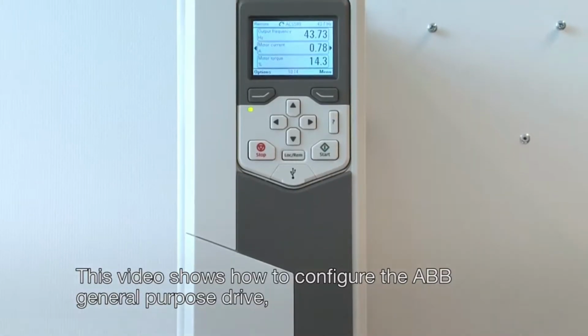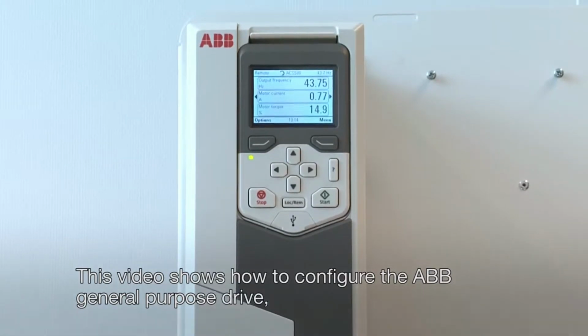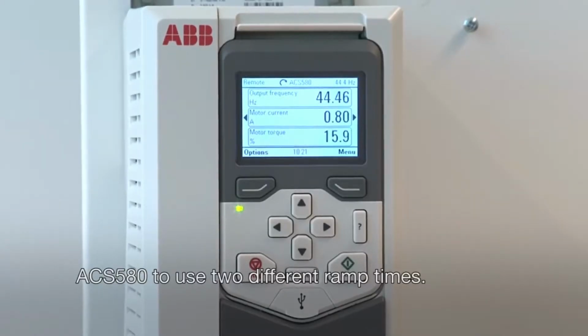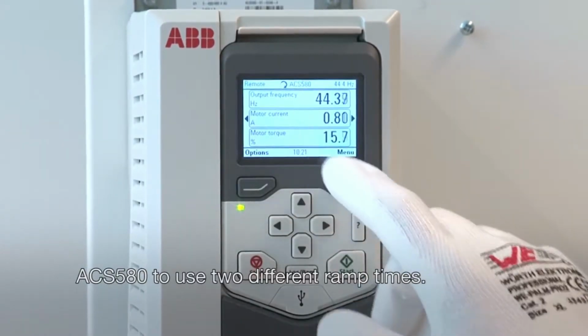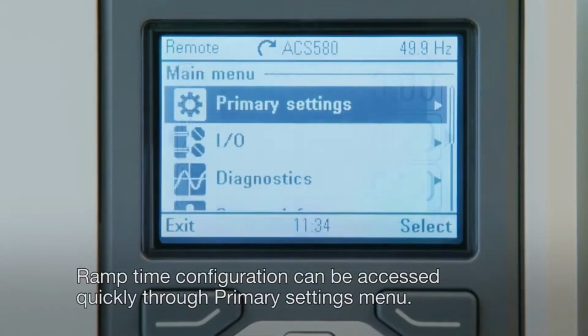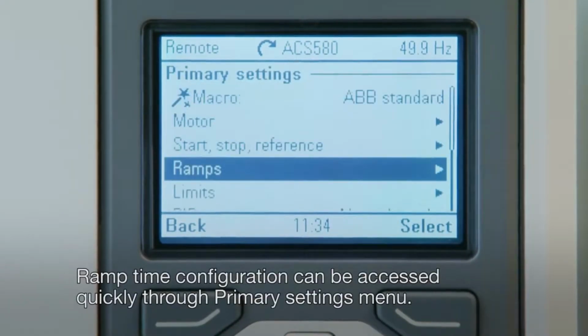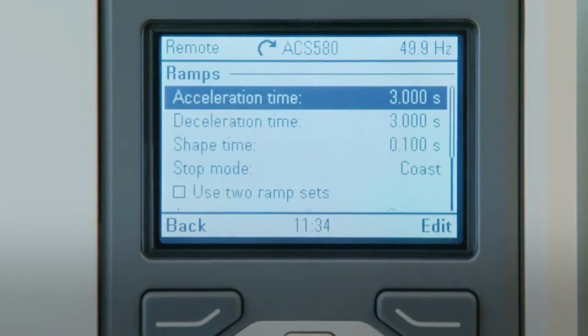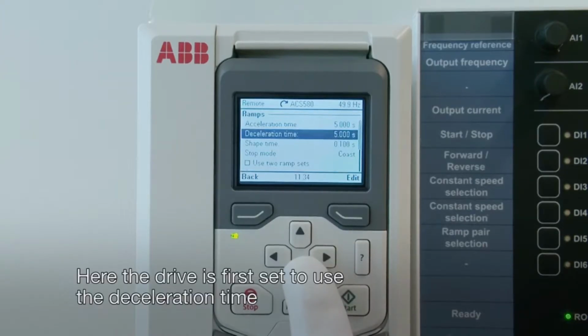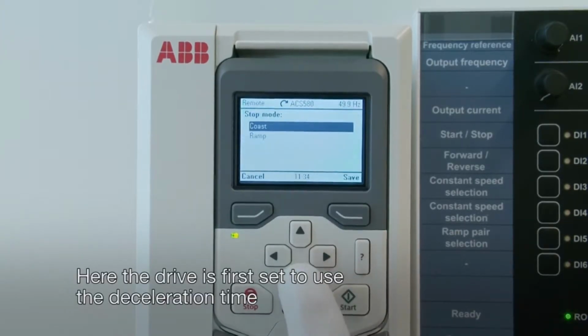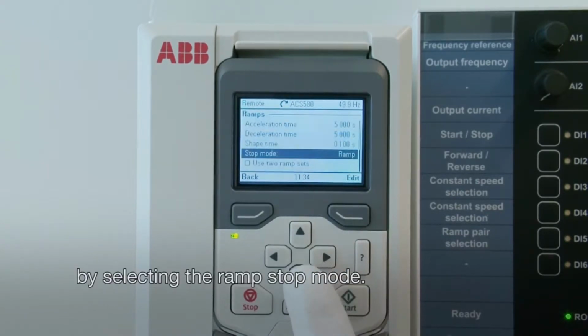This video shows how to configure the ABB General Purpose Drive, ACS580, to use two different ramp times. Ramp time configuration can be accessed quickly through the Primary Settings menu. Here the drive is first set to use the deceleration time by selecting the ramp stop mode.